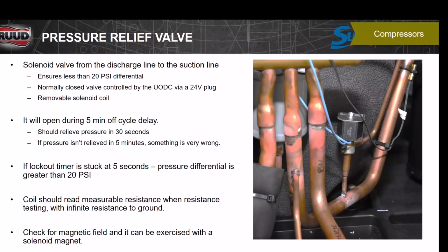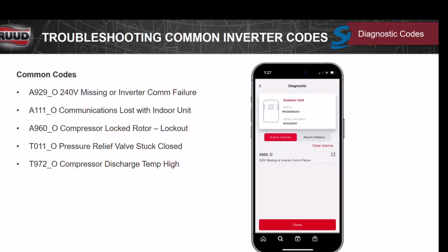Here's where the discharge line solenoid hooks up; it equalizes the pressures across the compressor. A common code you could see is missing inverter, COM code, A929_O. I see that a lot. That's if we're missing the 240 volts outside for some reason. Communications lost with the indoor unit, A111. I see that quite often. That's normally because we have a broken wire or a pinched wire, something shorted out somewhere. A960_O compressor lockout: we do occasionally see that, and most of the time it involves a thermistor bad or short cycling or something like that, where the compressor sees something that's going to hurt it.